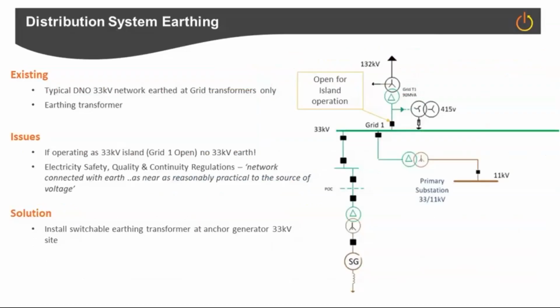Okay. System earthing is another issue. Typically the distribution networks are earthed at the 33 kV side of the grid transformers, 132 to 33 kV grid transformers. So when you've got a power island established and a DRZ established, in this example, the grid 1 circuit breaker would be open. So you've lost your earth. The electricity regulations over here, certainly, and I'm sure over in the US as well, but certainly in the UK, the network needs to be connected with earth as near as reasonably practical to the source of voltage.